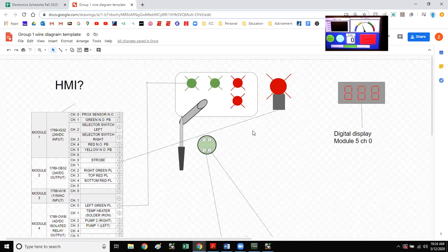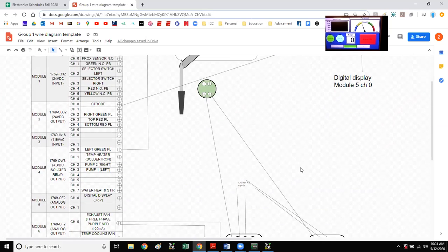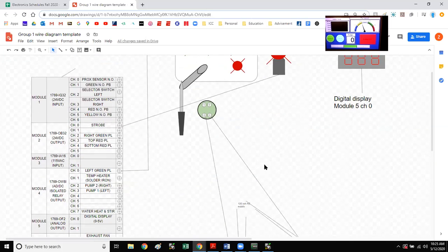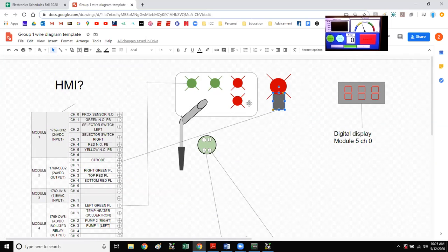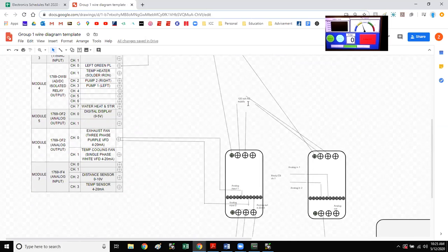Yeah, and then the strobe light, this is fine. On a wiring diagram, you don't want all these diagonal lines. You could have a bus of wires right in the middle, where this came down and then went over and then down. Everything comes down to the middle, over, and then where it needs to go. Okay. There's nothing wrong with what you're doing, but you need a neutral on this. It could just come from the power supply.